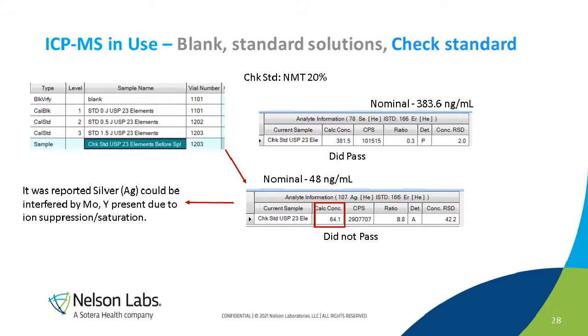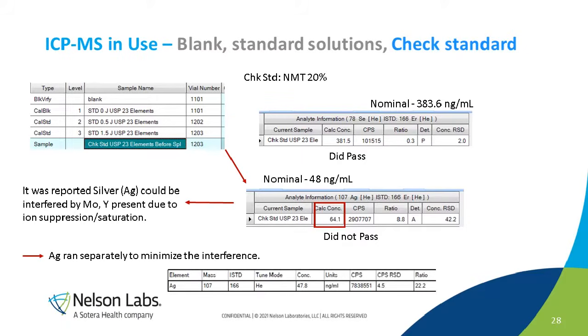Now I was talking about why it is 23, not 24, because of this. So when we check this silver, the number is 64.1. But in reality, the nominal number was 48 nanogram per milliliter. Did not pass. Why did this happen? It was reported that silver could be interfered with by other elements such as molybdenum or yttrium present, due to ion suppression or ion saturation. So if silver could be interfered with by other co-present ions, that's where the numbers are a little bit, I should say, unstable, a little bit high.